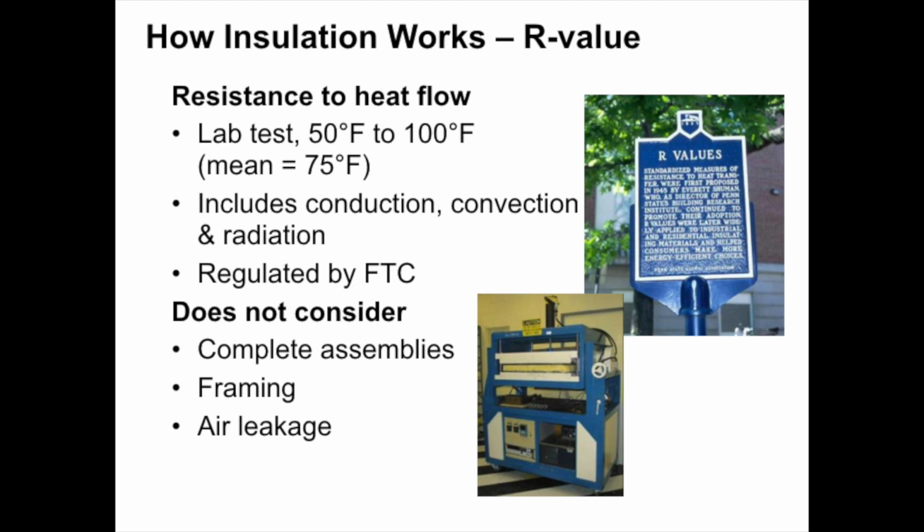This rule was put in place back in the 1970s because the same insulation material can provide a different R value at different test temperatures and at different thicknesses. And so the R value rule was established to create a level playing field so that R value claims could be compared by people who weren't engineers or scientists.